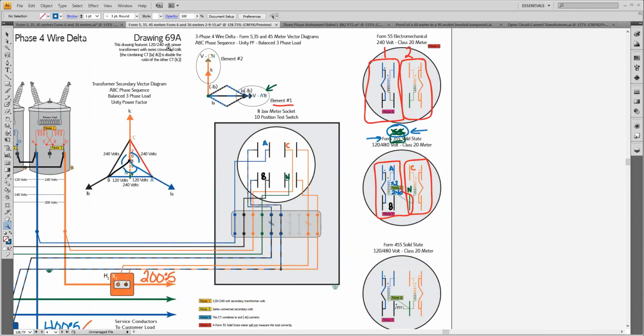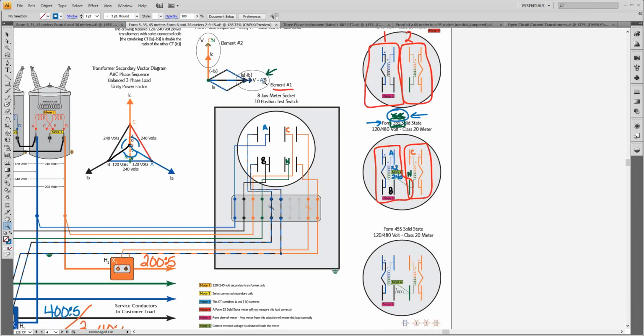Okay, so same vector diagram as we always had. Same vector diagram here. 5S here. Same correct metering because they multiplied this 120 volts to create a voltage that says 240 there. With the 45S, this was the GE replacement for the 5S. When we had the 45S, same vector diagram, like I said. Current inside both CTs exactly the same. Like I said, the current hasn't changed. It's the potentials that are being affected through this process.